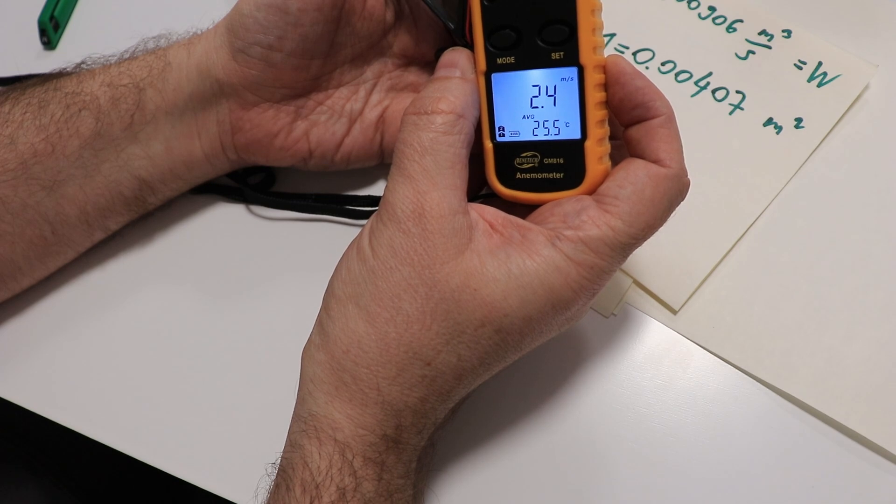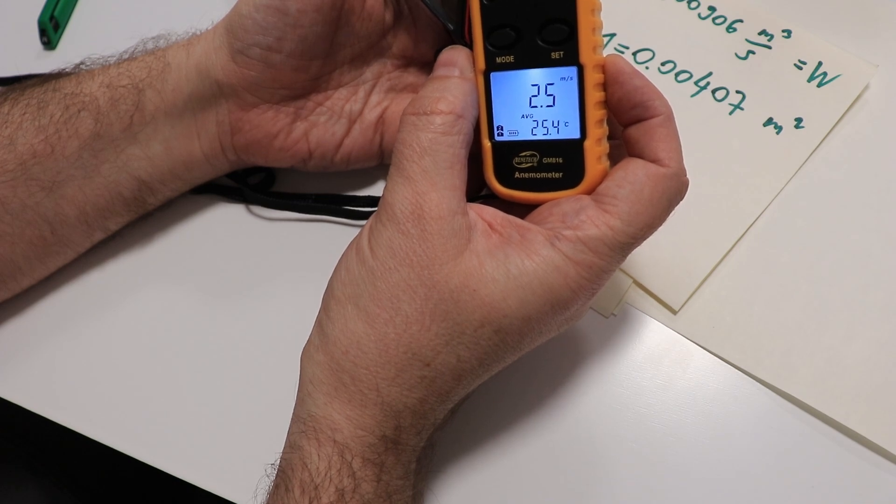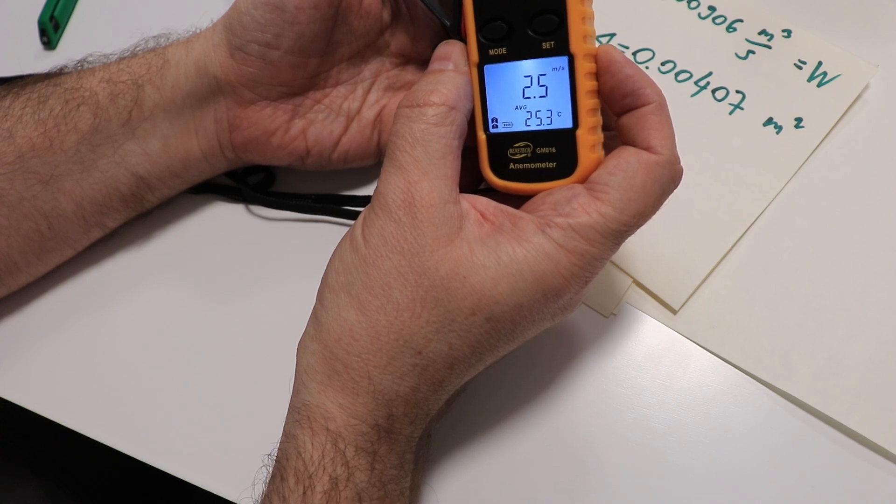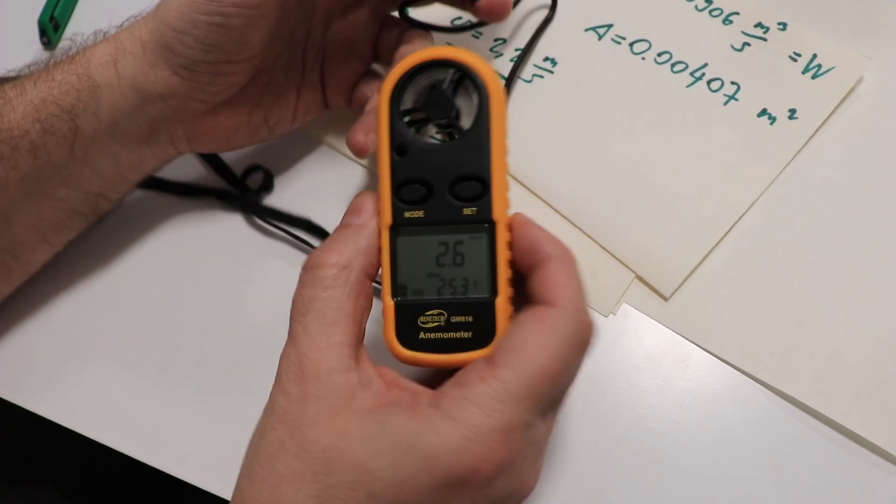I got approximately 2.5 to 2.4 meters per second average velocity. This means one of these three elements is incorrect, and I believe that's the specification of the fan.